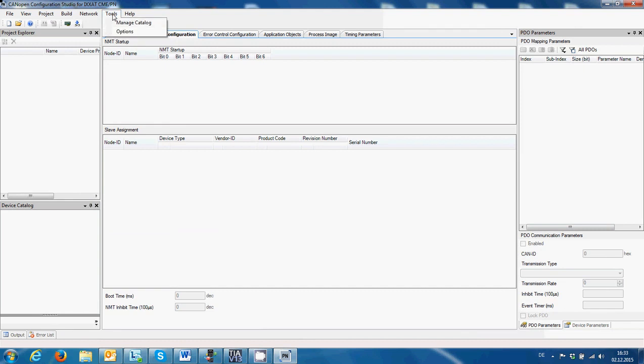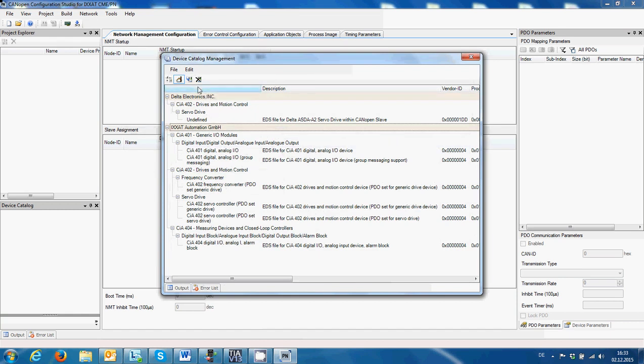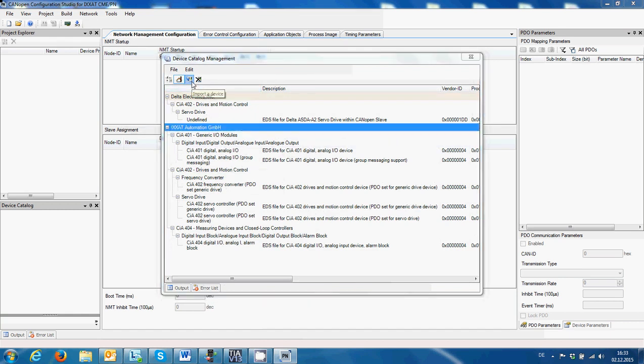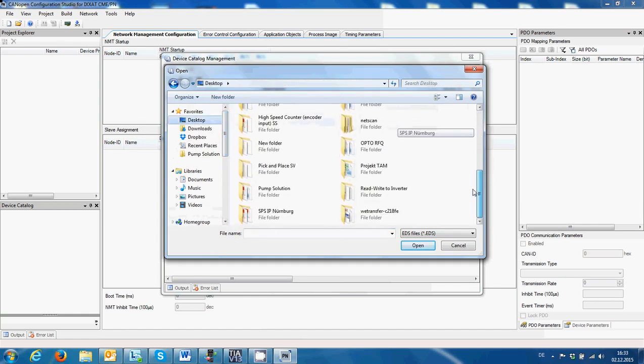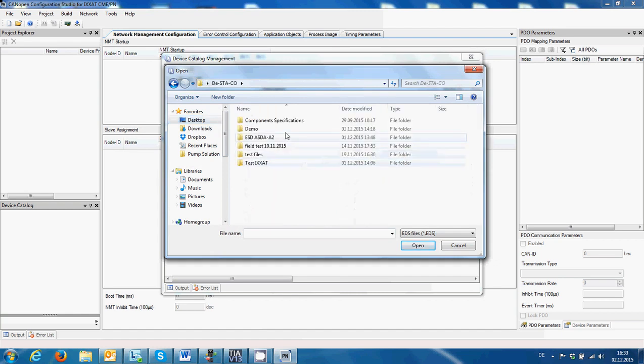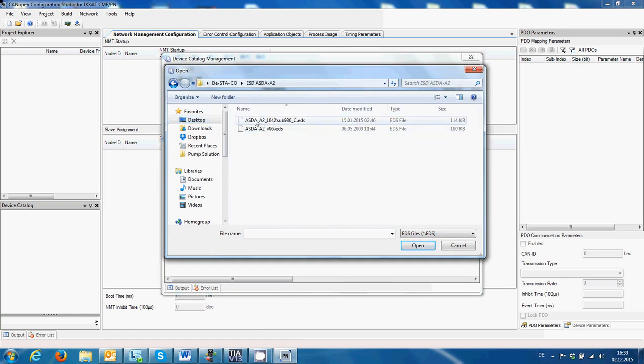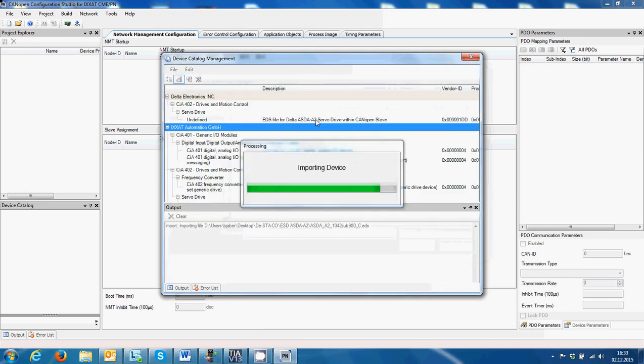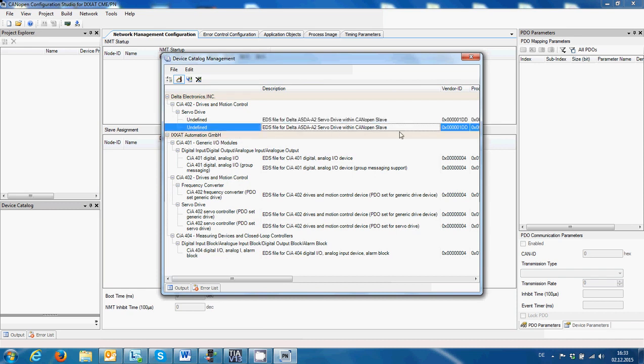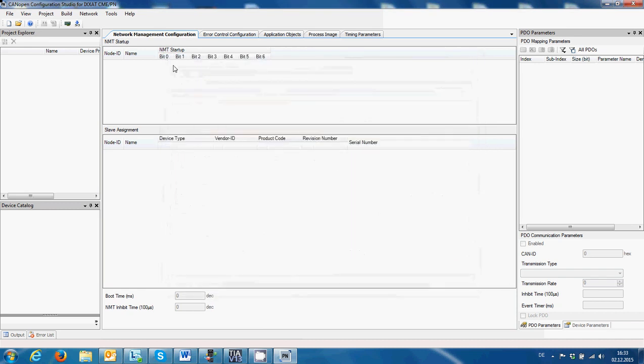The first step is to install our EDS file from the ASDA-A2 drive to the catalog of this software. We go to Tools > Manage Catalog, then we go to Import a Device, and then we can select the file downloaded from the website. Be careful — there are usually several versions; the version that works is the one with this specific file extension. Now we have the device here under Delta Electronics.